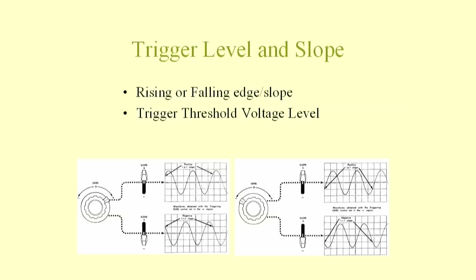Also, we're going to see some controls for trigger level and slope. The way to think about this is the slope is usually positive or negative, and then there's a voltage threshold, the level. This is typical of the controls you'd see: a level control that can go plus or minus, and a slope control. In this case, if I've got the slope set to positive and the level set somewhere positive here, we're going to send this sweep off when this voltage that's swinging back and forth crosses that threshold right there.